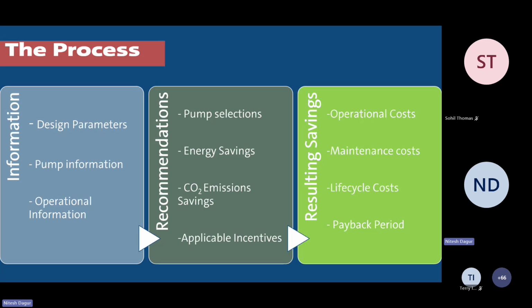For the hydronic pumps, or pumps anywhere in the HVAC loop and not in the boosting application, we do not usually resize the pumps. It is a like-to-like replacement, but we give you the best solution that would apply and that would save a lot of energy. Saying that, we very carefully use the term resizing because there have been times when we have suggested a higher capacity pump to the customer based on the needs.